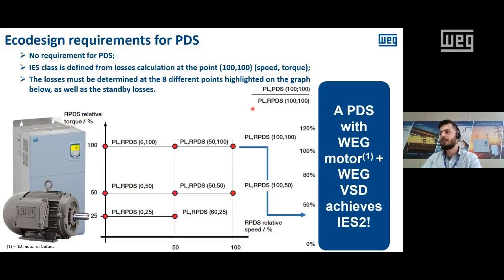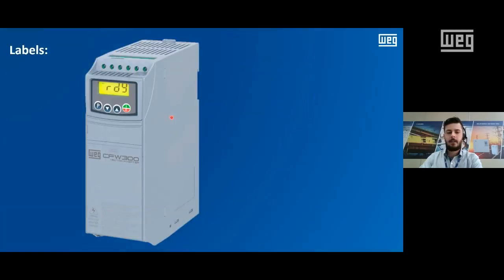A power drive system with a WEG motor plus a WEG variable speed drive achieves IES2. You have to take into consideration that you should use at least an IE2 motor or better. But if you combine these two, the result will be IES2 at least.